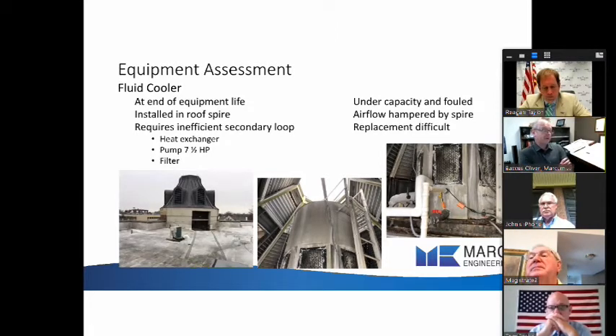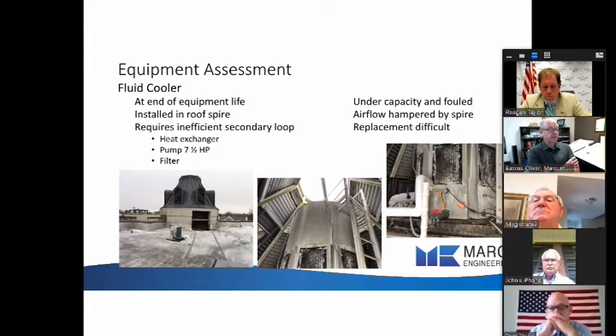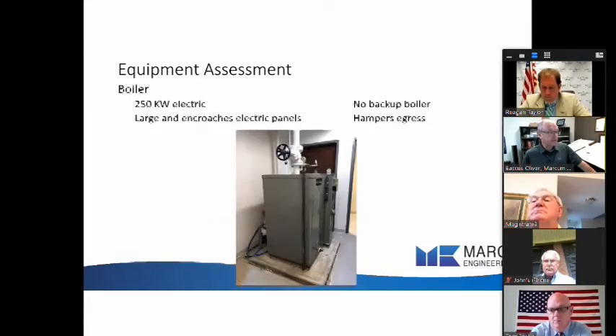What's really surprising is the unit is installed in the roof spire. The roof spire is shown on the left picture there. And what's not good about this is this hampers the airflow. These units have to have copious amounts of airflow. And I wouldn't have put it in this spire because that just restricts airflow. So I believe that is another reason we are short on cooling at times. Because it was done this way, this system requires an inefficient secondary loop, which is another heat exchanger, another pump, 7.5 horsepower, and a filter. I will note by being in the spire that replacement's difficult. So if I was giving this a school grade, this system's getting a D. D minus maybe. It's something we've got to contend with within a year.